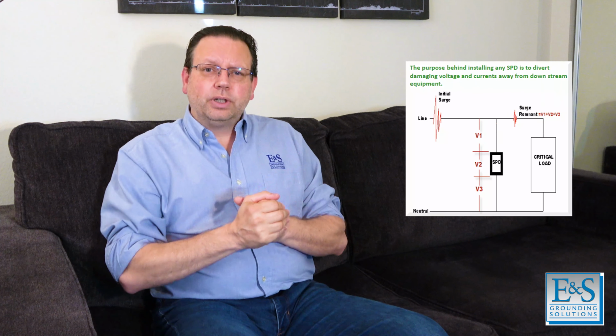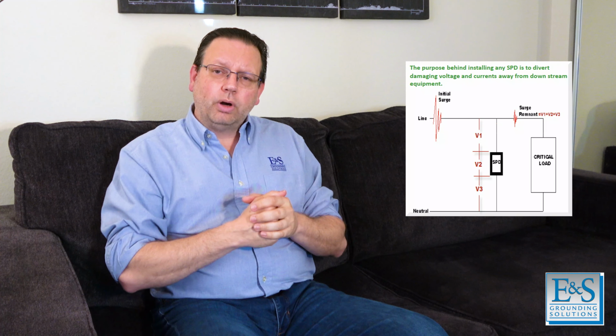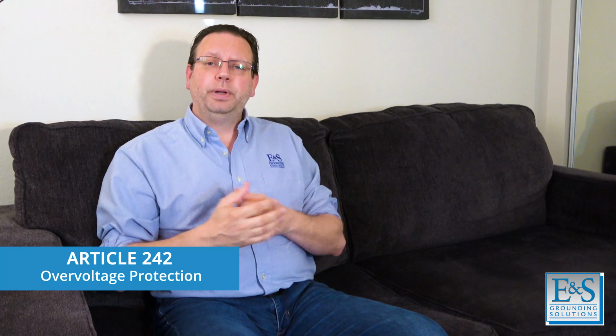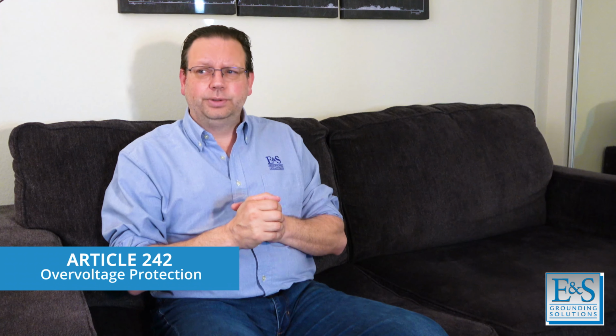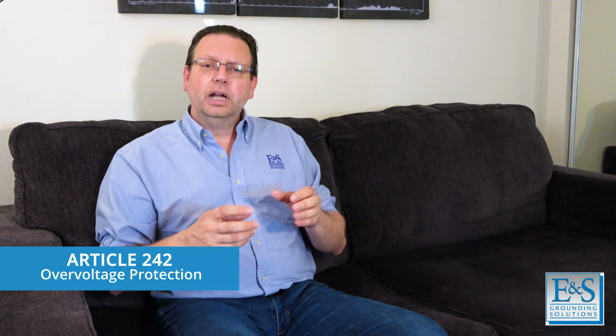The third component that we utilize in lightning protection systems is surge protection devices. And we see this now in, I believe, Article 242. It's a brand new article within the National Electrical Code. If you're in the IEC, you've been requiring this since at least 2008, maybe even earlier. And what we're doing now is cascaded surge protection systems.